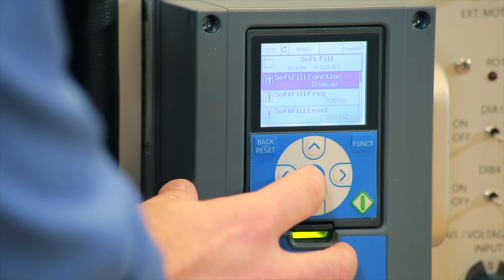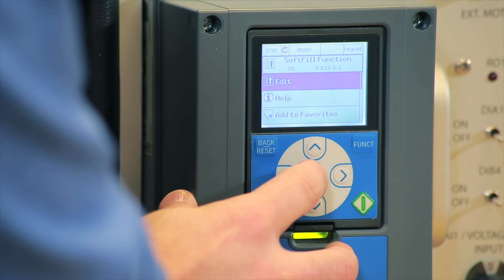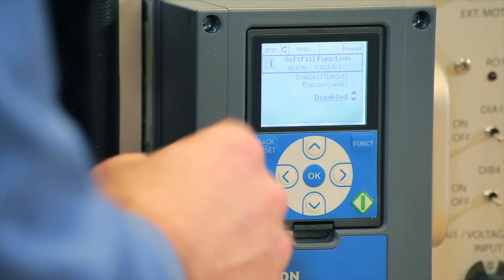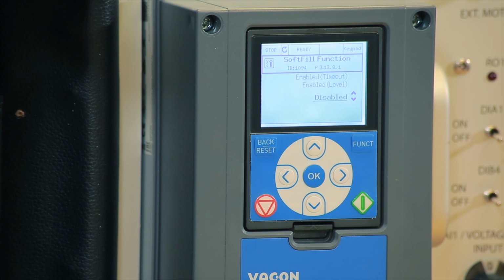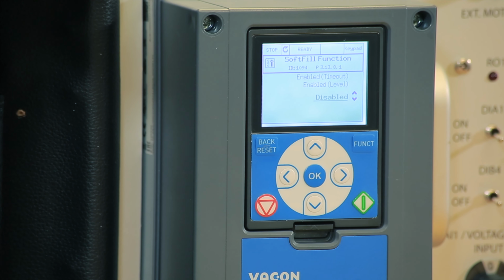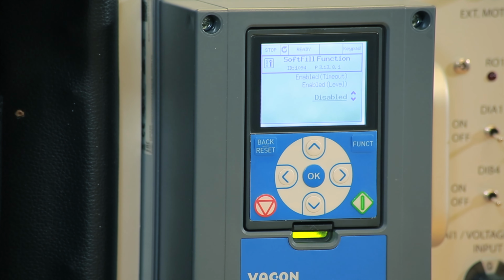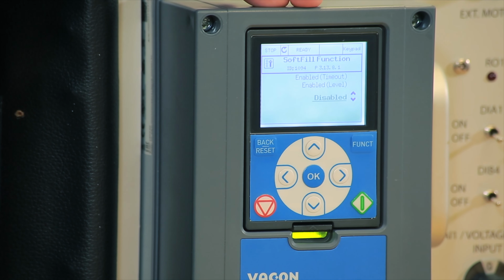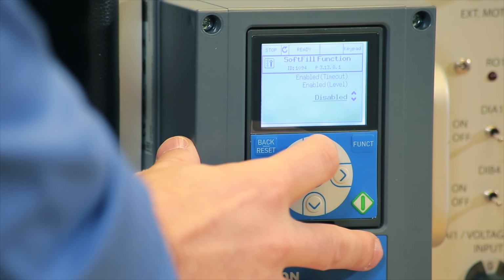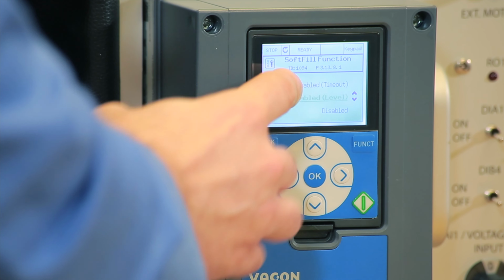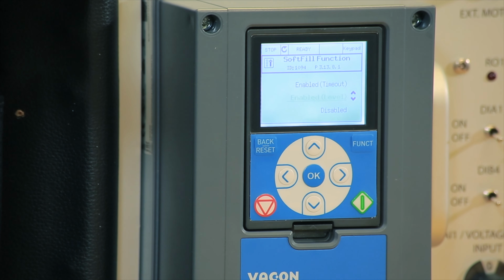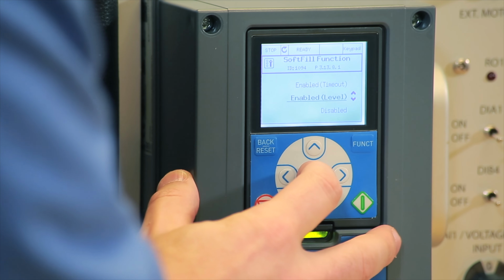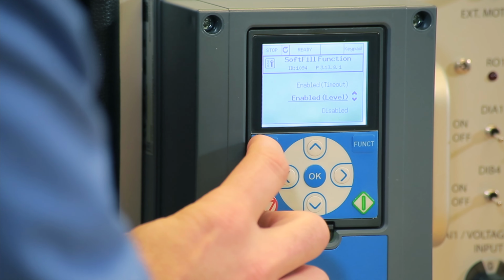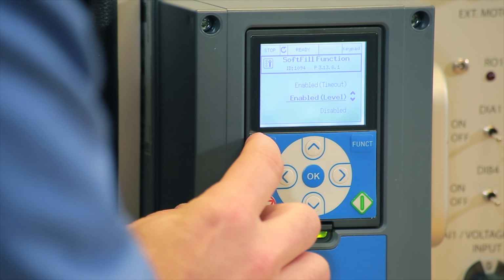Once we enter PID controller, we're going to find something called soft fill, and this is where we're going to go. So right now the soft fill function is disabled. We want to enable it. So here we go, we have two choices. We can soft fill a pipe up to a particular pressure level, or we can soft fill a pipe up to a predetermined amount of time. So for our scenario, we're going to choose level, which is up to a particular pressure level. We're going to click OK. Enabled level.